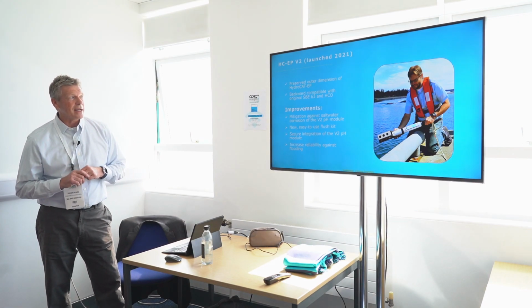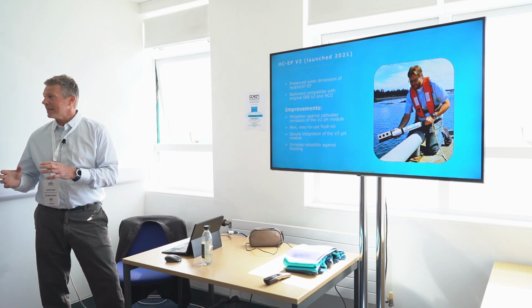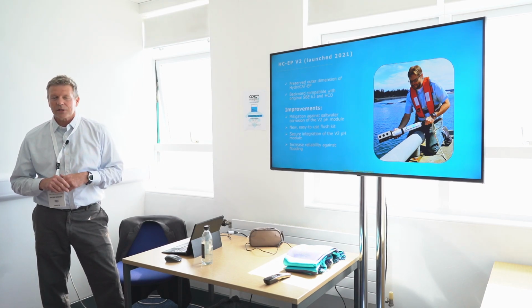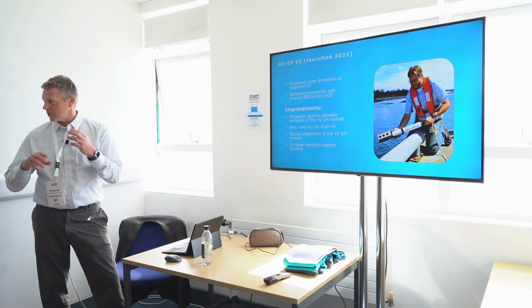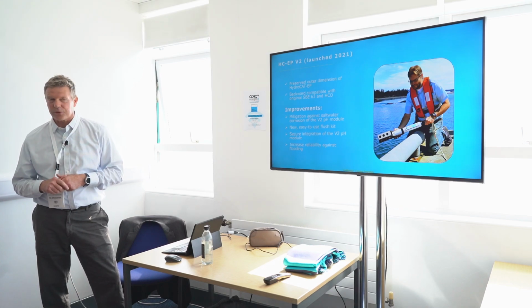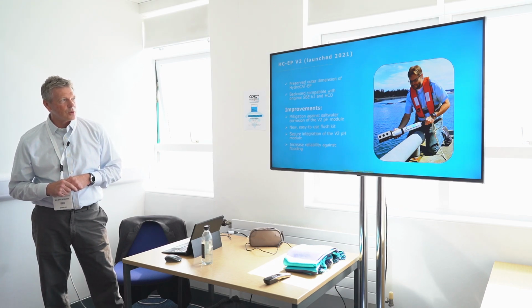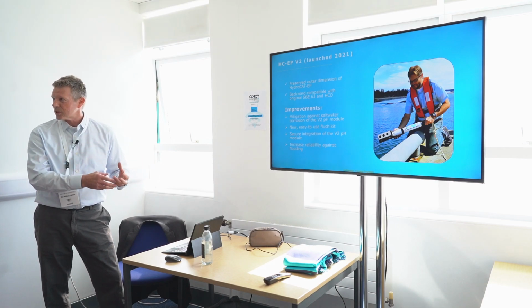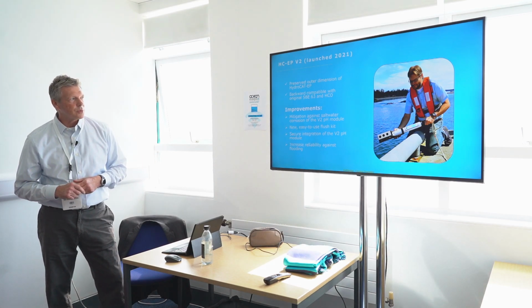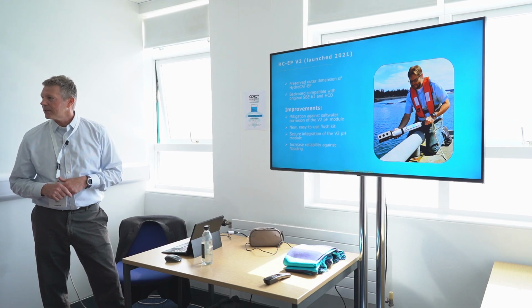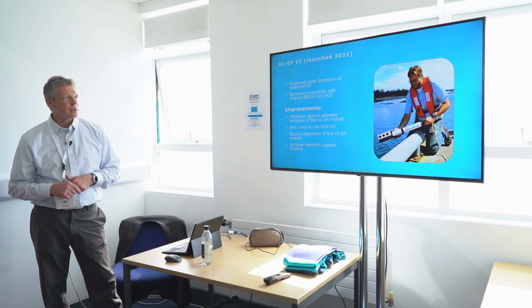We try to maintain backwards compatibility, in the sense that if you have a deployment configuration, there's no change to outer diameters of the instrument. Also, if you want to upgrade your sensor from an original system to the new system, you can reuse your DO sensor and the optics. So there's no changes to that.